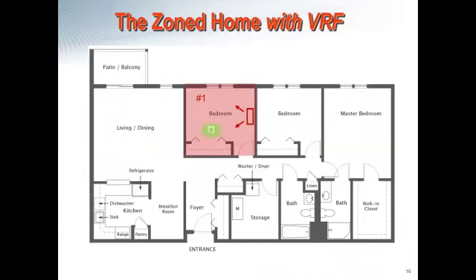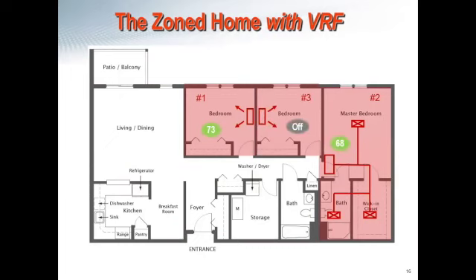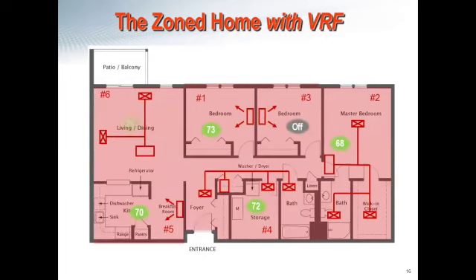So what we're going to do is, and I'm going to fast forward through some of this for you guys, but the point I really want to hammer home is that each individual zone can be turned on or turned off to a different set point and only provide a specific amount of heating or cooling that is going to be required for that space. As you can see, your foyer, your storage area, and your bathroom, those are going to be probably somewhat underutilized zones.